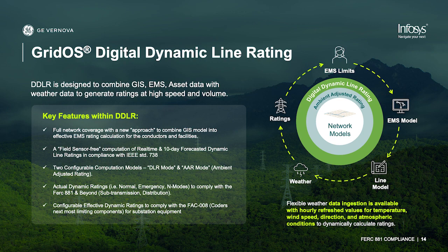Whereas with GE's digital dynamic line rating, you're taking into effect not only the ambient temperatures, but also the wind speed, wind direction, irradiance, et cetera, so that you get the full cooling effect on your transmission lines, and you get the maximum capacity available out of those lines, which will greatly reduce the transmission congestion on the electrical grid.